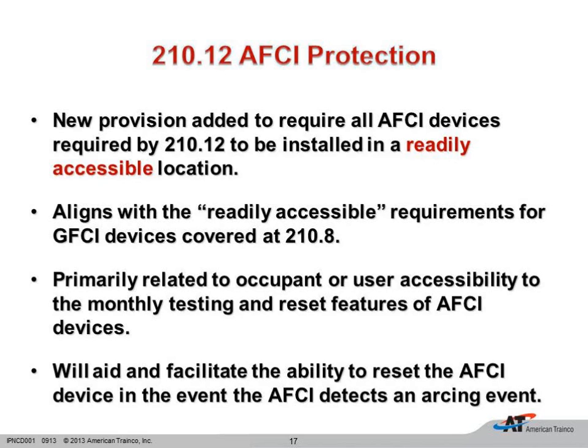So outlets or devices in the following rooms, and they've added kitchens. So kitchens now will have to have arc fault circuit interrupter protection. And they always had family rooms, dining rooms, living rooms, parlors, libraries, dens, bedrooms, sunrooms, recreation rooms, closets, hallways. All those rooms were in the 2011 version of the National Electrical Code. But they did add kitchens, and they also added laundry areas. So our washing machine will also be part of this AFCI protection.